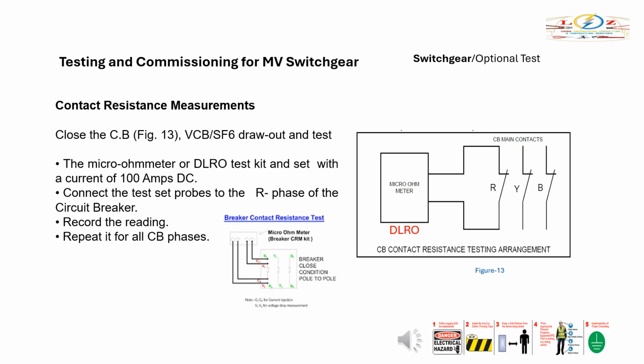Contact resistance measurements. Close the CB as shown in Figure 13. The VCB or SF6 must be drawn out and tested away from the switchgear panel, or the breaker elements can be removed from the switchgear cubicles on wheel rollers for this testing.